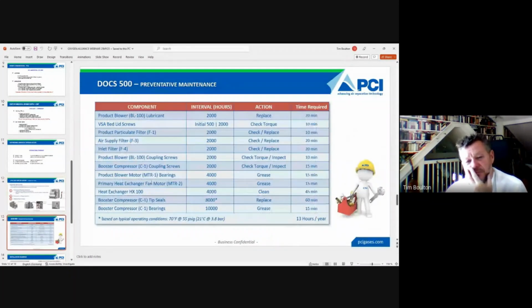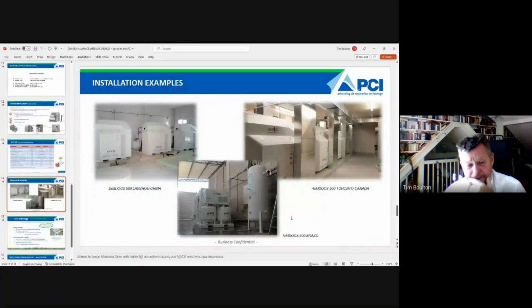We talked about the service and maintenance of VSA systems as being a lot less than for PSA. Here is just a list of components, intervals, and time required for a DOCS 500. That's a 500 liter per minute, a 1 ton per day unit, 500 liters per minute of oxygen. As you can see here, typically you'll need around 13 hours per year. So all of you that have dealt with PSA systems, you'll know that that is a substantially lower amount than normally required for a PSA.